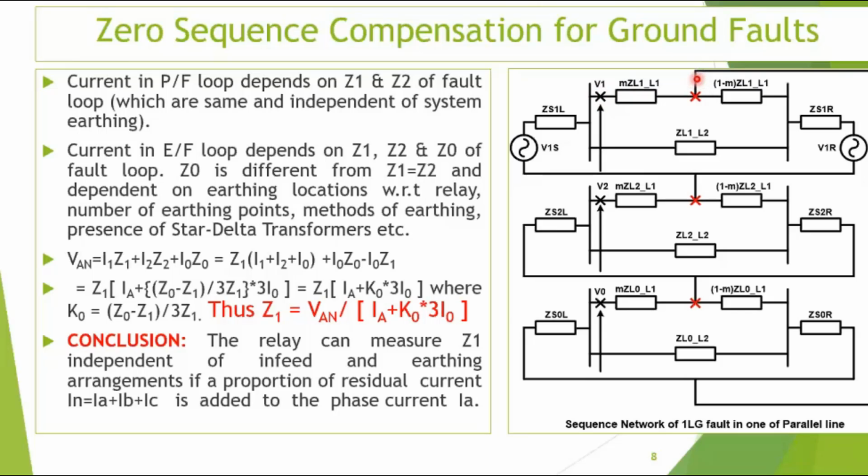And if I have a fault resistance, that fault resistance will also come into this loop, this equation. So V1 over here does not represent the actual voltage with respect to the zero potential path. V1 over here, what I have drawn, represents the voltage difference from this to this. V2 is also the same and V0 is also the same. Now, how does this thing help?